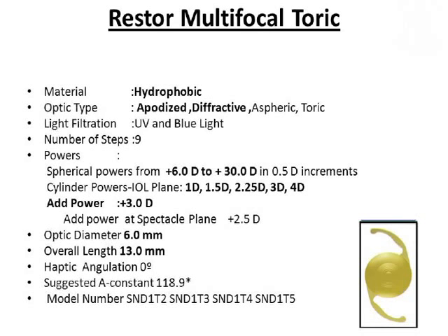The second is the Restor multifocal toric IOL. It is a hydrophobic, apodized, diffractive IOL with 9 diffractive steps. It is available in spherical powers from +6 to +30 diopters in increments of 0.5 diopters, and cylindrical powers from 1 to 4 diopters. It has an add power of +3 diopters. The optic diameter and overall length are the same as the Tecnis — 6mm and 13mm respectively.